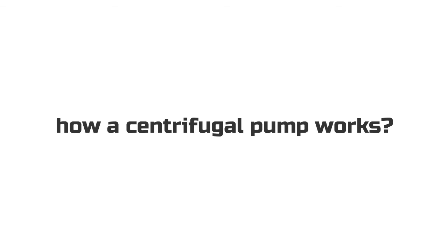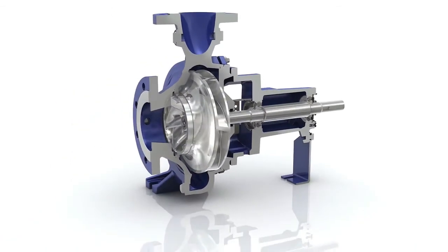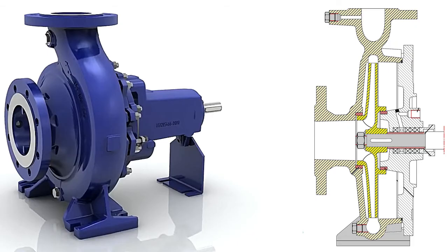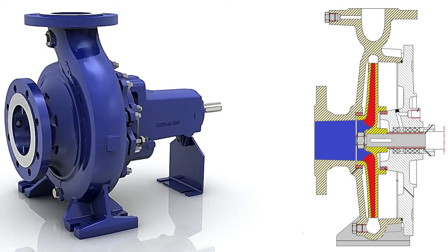Like most pumps, a centrifugal pump converts rotational energy, often from a motor, to energy in a moving fluid. A portion of the energy goes into kinetic energy of the fluid. Fluid enters axially through the eye of the casing, is caught up in the impeller blades, and is whirled tangentially and radially outward until it leaves through all circumferential parts of the impeller into the diffuser parts of the casing. The fluid gains both velocity and pressure while passing through the impeller.